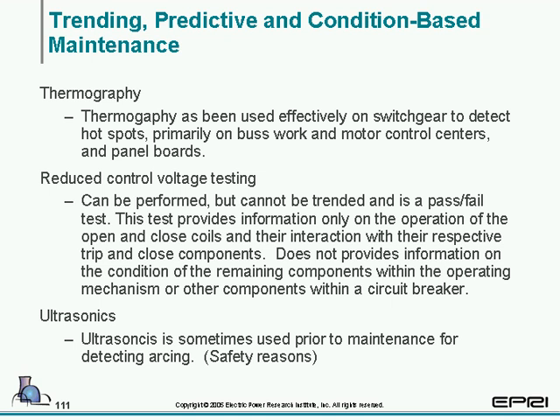Thermography, we have had some success with thermography. Obviously, like motor control centers, panel boards, that type of thing. Thermography is very effective in defining and locating hot spots. You can do reduced control voltage testing. It's typically not trended. It's a pass-fail test, but it does provide some information on the operation of the open and closed coils and their interaction with their respective trip and close components. It does not provide an overall condition of the circuit breaker.